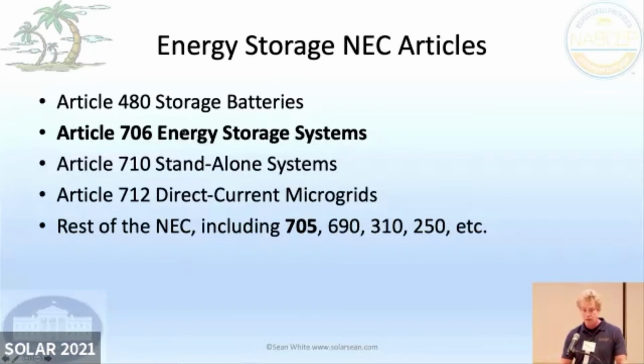And so when they came out with 706 in the 2017 NEC, the intention was to get rid of 480. But then what happened was some people didn't want to get rid of it. And a lot of it probably has to do with the telecom guys. The telecom guys, they don't need to change their ways. And I don't really blame them, but they have this thing behind a fence. It's not in your garage. It's not like your kids are going to be walking around it. They don't want to have a disconnect or something like that. So it's kind of interesting that for a lot of these lead acid batteries, NiCad batteries, you don't even need a disconnect.